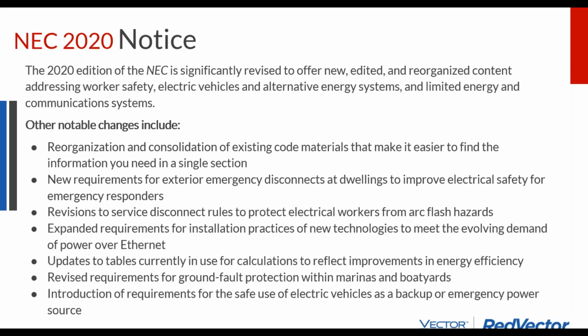Let's talk about some 2020 changes. The one that I find most interesting is the concept of an exterior disconnect switch for utility personnel to come up to on the outside of the building, and they turn that switch from the on position to the off position, and it shuts down the on-site power systems. So, imagine a panic button, but it's on the outside of the building rather than the inside, and it can turn off all the power to the building. And not all building professionals have thought that would be such a good idea because that means anybody out there can come and turn off power to your building.